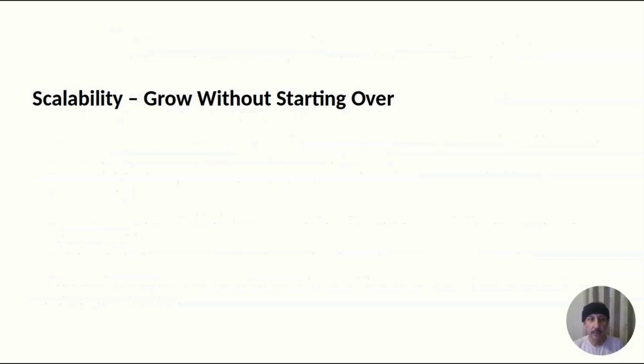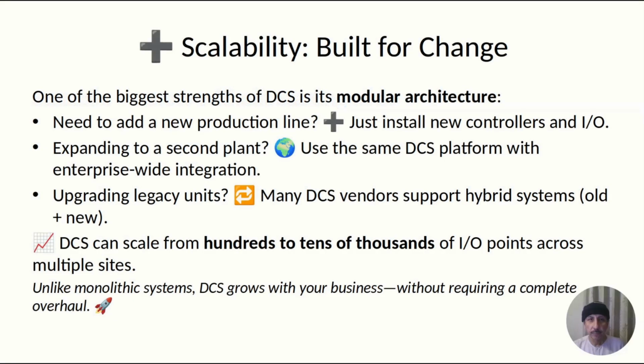Scalability. Grow without starting over. One of the biggest advantages of DCS is scalability. Imagine you start with one production line, later you add a second. With the DCS, you simply install new controllers and I/O racks, connect them to the same network, and integrate them into the existing HMI. No need to rip or replace anything.